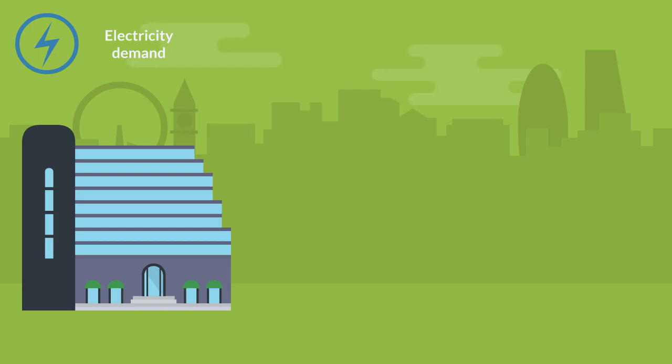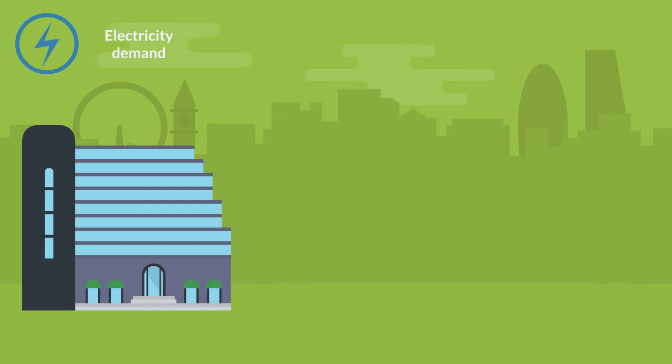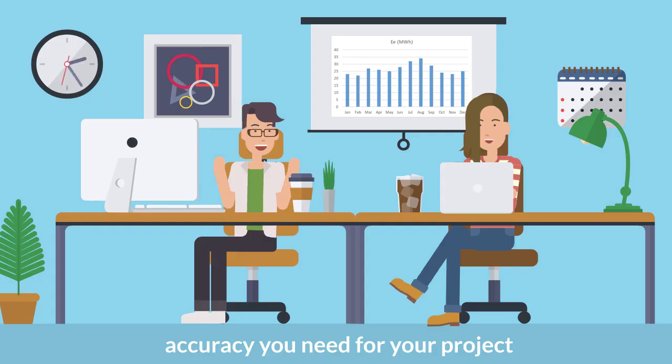Ideally, a site's electricity demand profile should explore the daily variation in electricity demand with at least hourly resolution. This is helpful to identify the peak power demand over a daily cycle. Seasonal variations along a 1 year period. This is helpful to assess the type of renewable energy supply sources that can be considered. Okay, but on what parameters does the electricity demand depend?